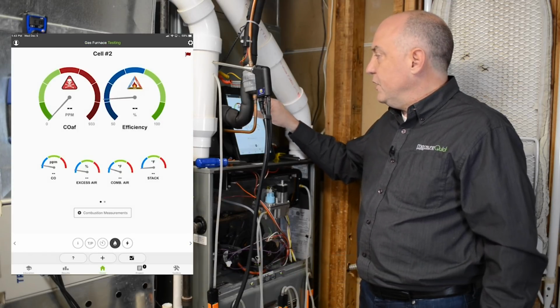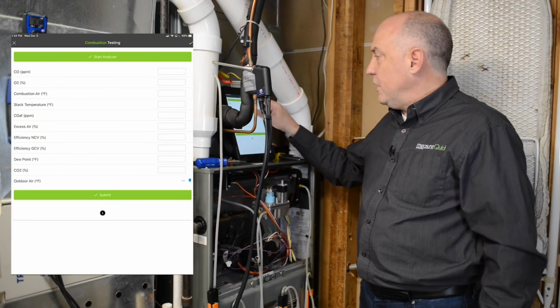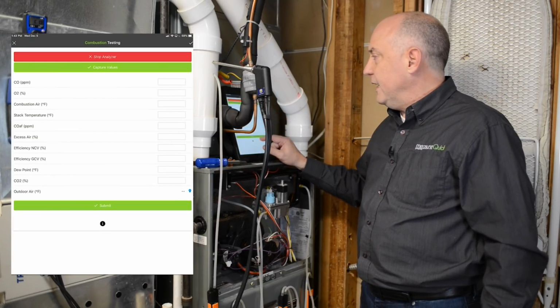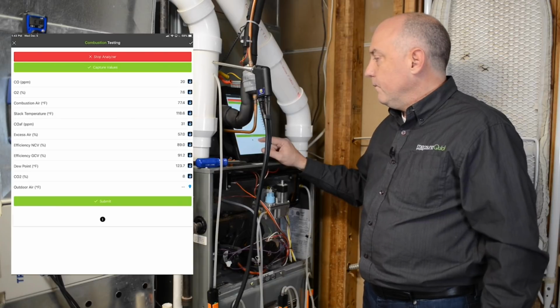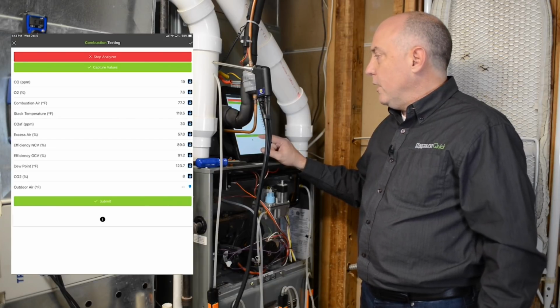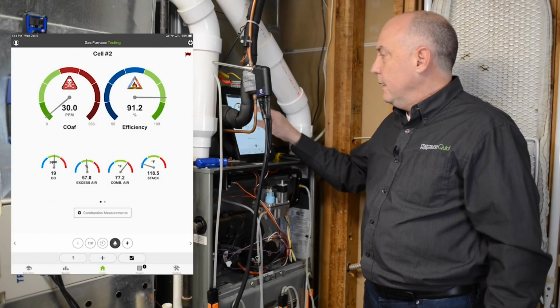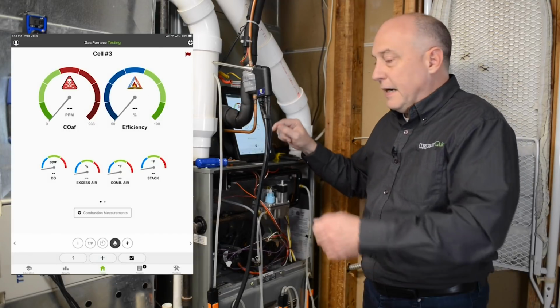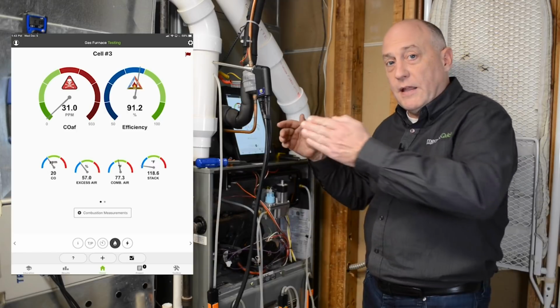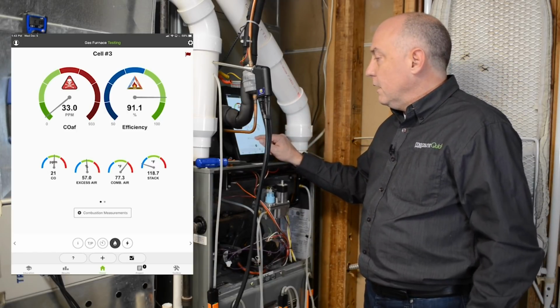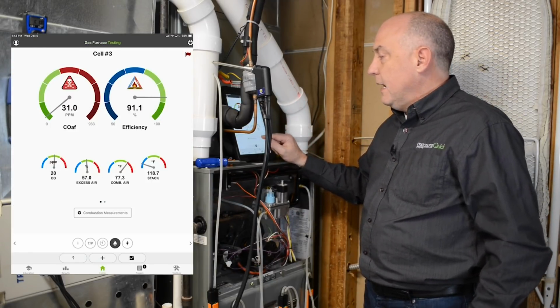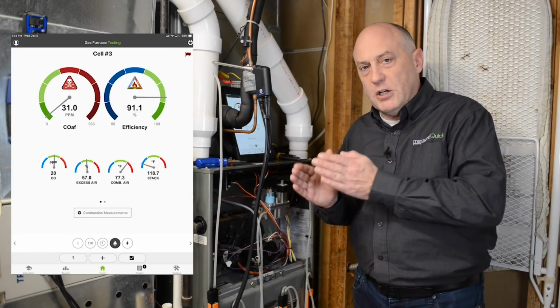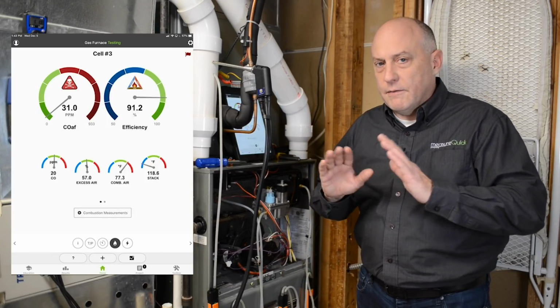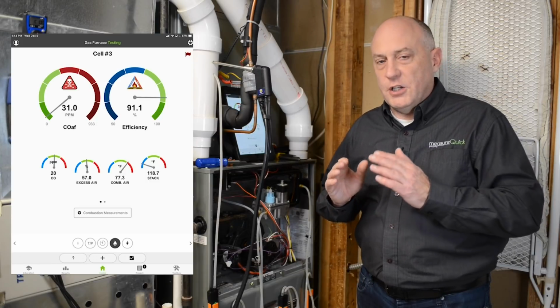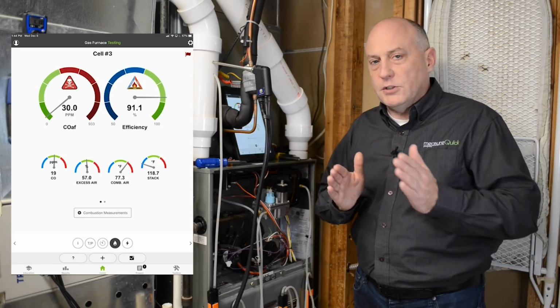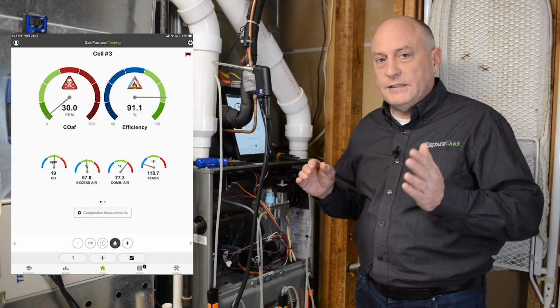And then I'll go to cell 2 and go back in the combustion measurements. We'll just restart the analyzer again here. It'll pull in those values. And so now we're pulling in all the values off cell 2. I hit submit, go to cell 3. And I'd have to physically move that combustion analyzer over to that 3rd cell. Move to the 3rd cell, go back in the combustion measurements, hit submit, and then it's going to pull all the data from all 3 measurements into the analyzer. So again, very, very handy feature on there. Allows you to get all the measurements you need. We can print all those now on a single sheet of paper and allow you to see all the combustion tests.